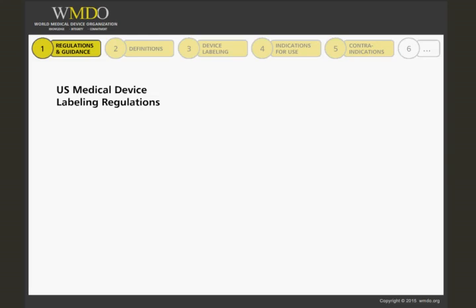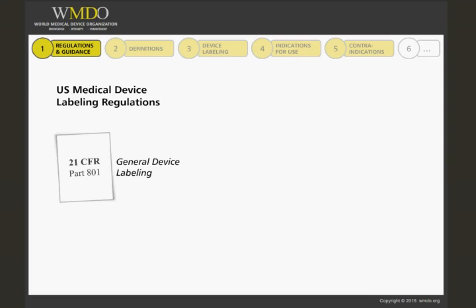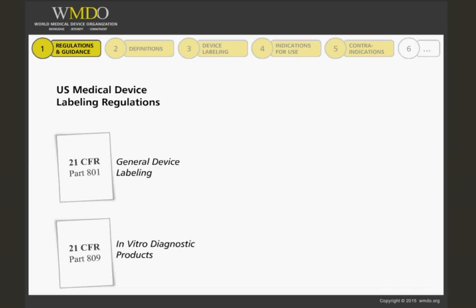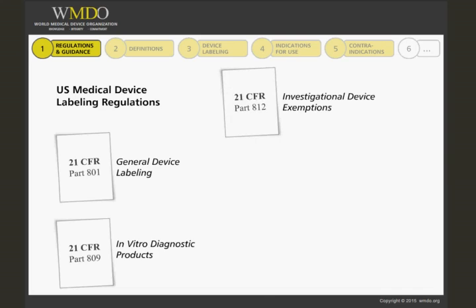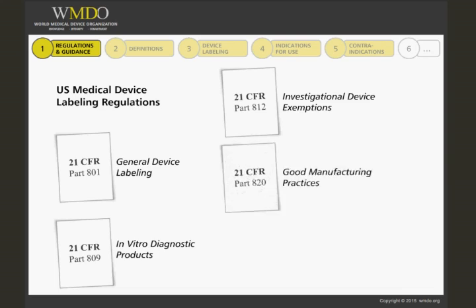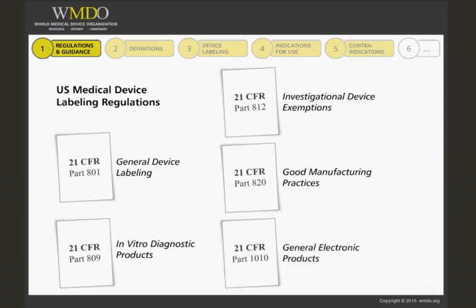Let's look for the applicable sections of Chapter 21 of the Code of Federal Regulations, or CFR. General device labeling is described in 21 CFR Part 801. In vitro diagnostic products is described in 21 CFR Part 809. Labeling in the framework of clinical investigations is described in Investigational Device Exemptions, 21 CFR Part 812. The Good Manufacturing Practices are covered by 21 CFR Part 820, and General Electronic Products are the subject of 21 CFR Part 1010. You may access and look up the sections on the FDA website.